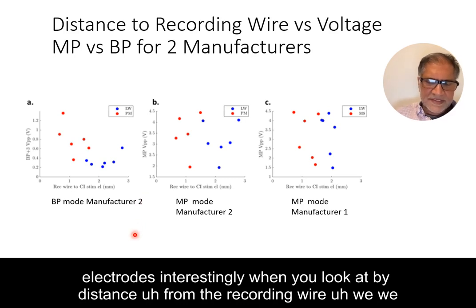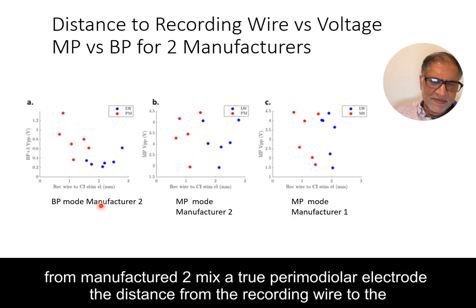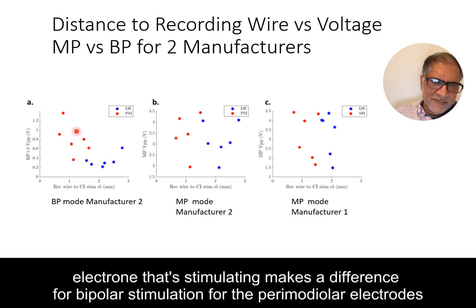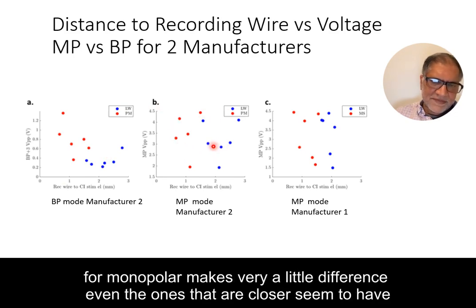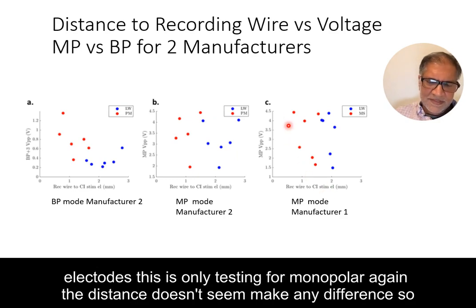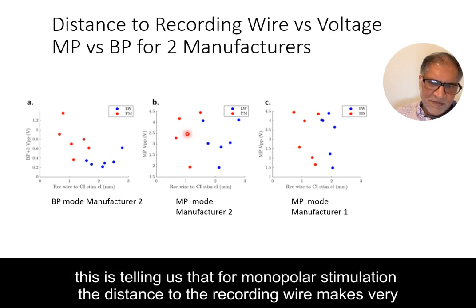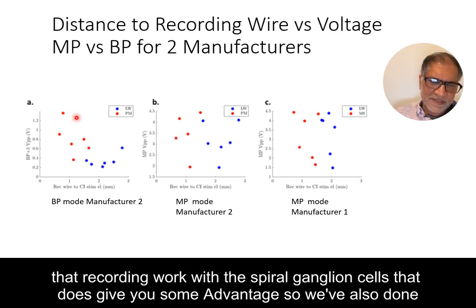When you look at distance from the recording wire, for bipolar stimulation with a true perimodiolar electrode, distance to the stimulating electrode makes a difference. But for lateral wall electrodes, distance doesn't matter as much since they're all quite far away, and for monopolar, distance makes very little difference regardless. This tells us that for monopolar stimulation the distance to the recording wire makes very little difference, whereas for bipolar stimulation, getting closer to the spiral ganglion cells does give some advantage.